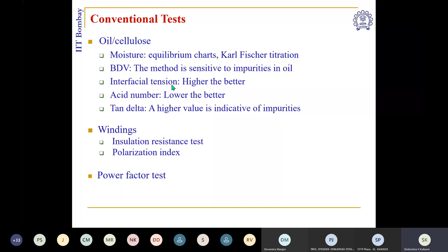And then there are, of course, other tests like excitation current tests. Suppose you have a core, and one of the limbs has some problem, then that phase excitation current will be different from the other two phases. Based on that, you can know the condition of the core, or even if there is a turn-to-turn fault, then the excitation current test can reveal some interesting diagnostic conclusions.